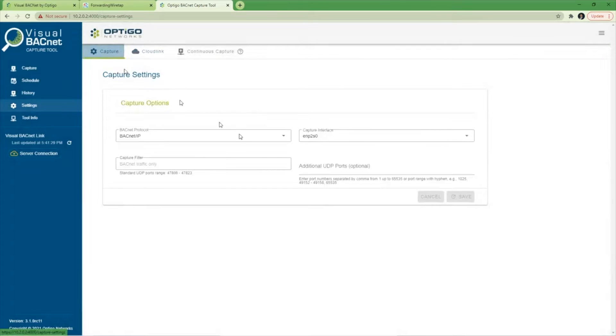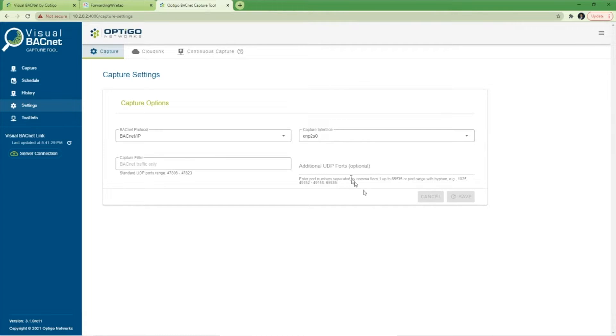Finally, in the capture options, configure the type of BACnet traffic you want to capture. I'll choose BACnet IP for this example. Under Capture Interface, choose the correct Network Interface Controller, or NIC, which can be found in the Windows Network settings of your computer. Next, configure which UDP ports to capture on. By default, the tool captures on the standard BACnet ports 47808 to 47823.